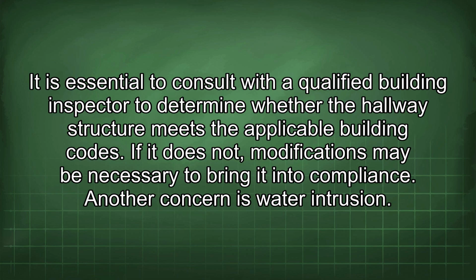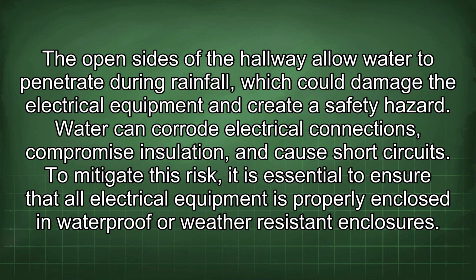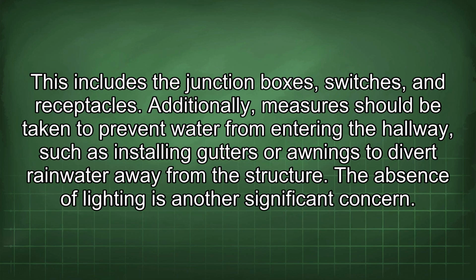Another concern is water intrusion. The open sides of the hallway allow water to penetrate during rainfall, which could damage the electrical equipment and create a safety hazard. Water can corrode electrical connections, compromise insulation, and cause short circuits. To mitigate this risk, it is essential to ensure that all electrical equipment is properly enclosed in waterproof or weather-resistant enclosures. This includes the junction boxes, switches, and receptacles. Additionally, measures should be taken to prevent water from entering the hallway, such as installing gutters or awnings to divert rainwater away from the structure. The absence of lighting is another significant concern.